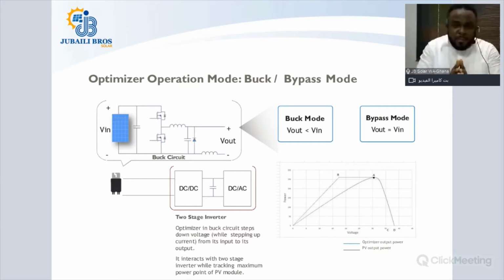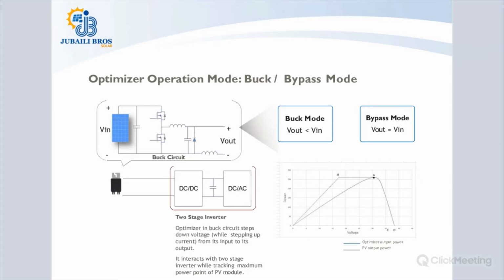But in the buck mode, what it does is that it reduces the output voltage of the PV module whilst increasing the output current. So that is how it operates. It will be important for us to identify these two modes of operation. It will be very interesting for my technical explanations later on about how the optimizer works. So it works in two main modes, the bypass mode and the buck mode. In the buck mode, the output voltage is always lower than the input voltage, which means the output current is always higher than the input current. And the PV optimizer is able to work with any two-stage inverter.